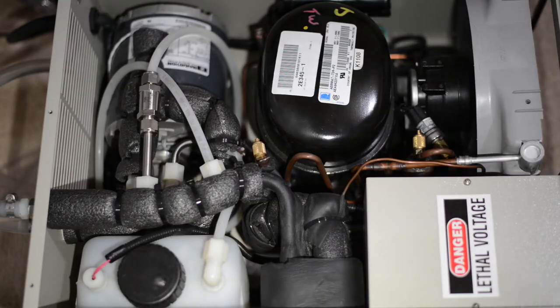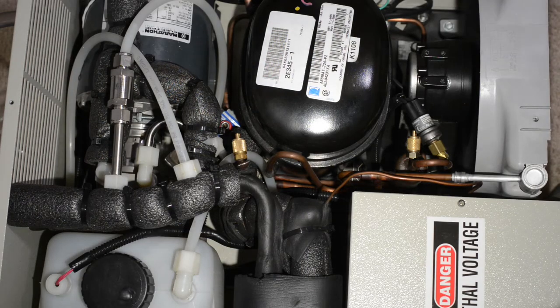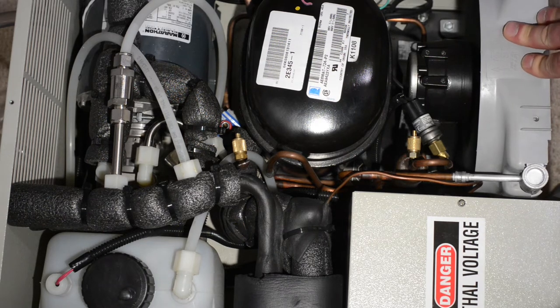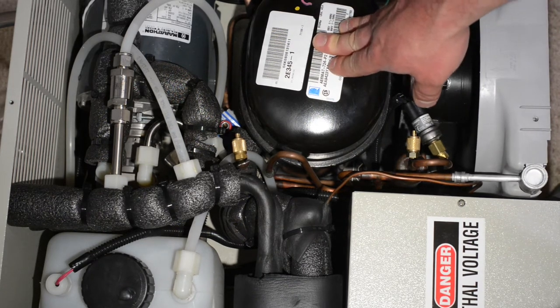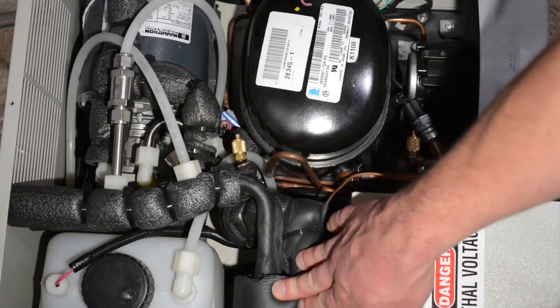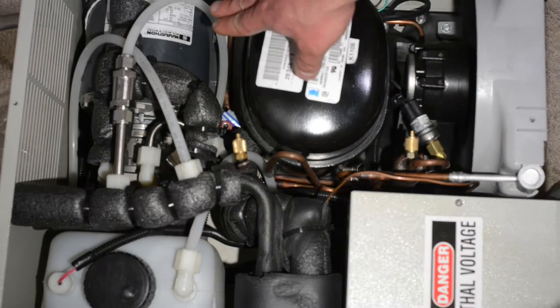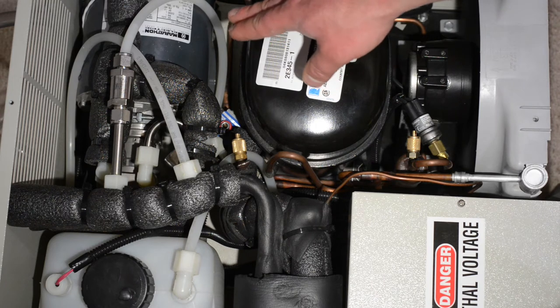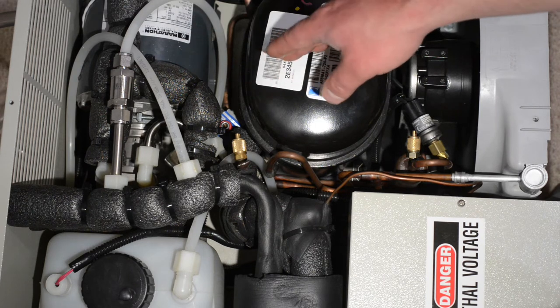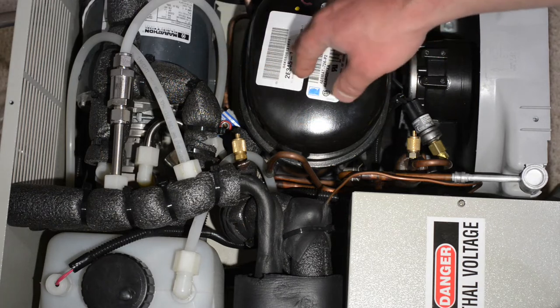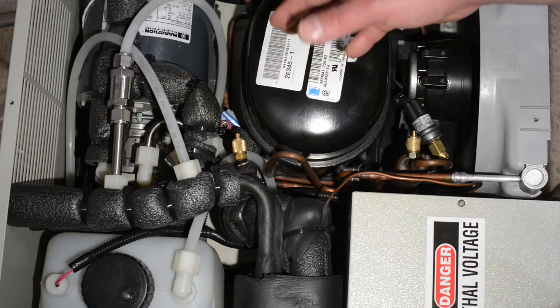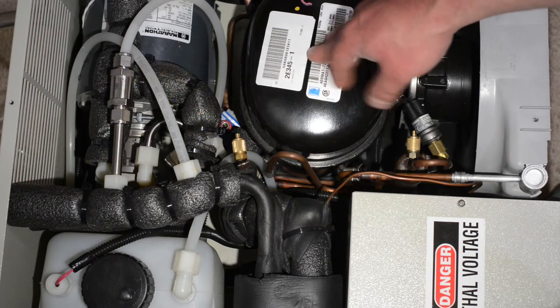Okay, so this is my industrial rack mount chiller. It's rated to remove 4,000 BTU or 1,200 watts of heat. So here are the various parts of the chiller. In the front we've got the condenser coil, then we have the compressor, and then we have the water to refrigerant heat exchanger. We've got a reservoir, and we've got our circulation pump. The circulation pump is a 1/3 horsepower rotary vane pump that flows at 1.8 gallons per minute up to 80 psi, depending on how restricting the lines are.